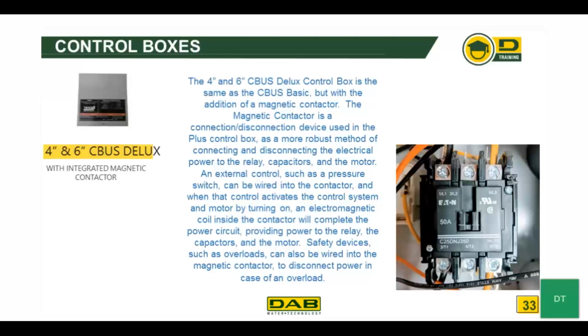An external control, such as a pressure switch, can be wired into the contactor, and when that control activates the control system and the motor by turning on, an electromagnetic coil inside the contactor will complete the power circuit, providing power to the relay, the capacitors, and the motor. Safety devices such as overloads can also be wired into the magnetic contactor to disconnect power in case of an overload.